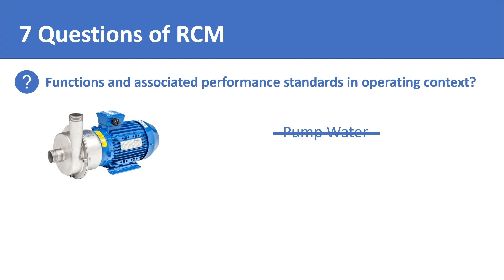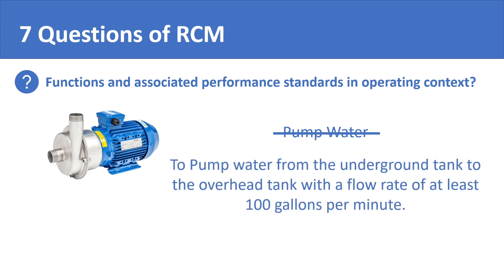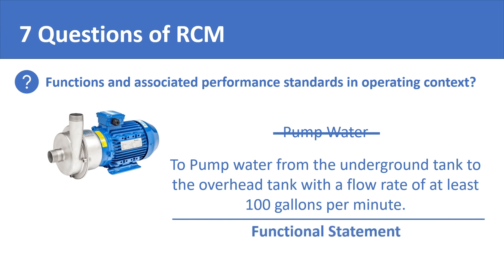A pump's function will be to pump water from the underground tank to the overhead tank with a flow rate of at least 100 gallons per minute. Now this is a proper functional statement in the context of reliability centered maintenance. It clearly describes what the pump needs to do and also lays down the performance standard in the operating context.